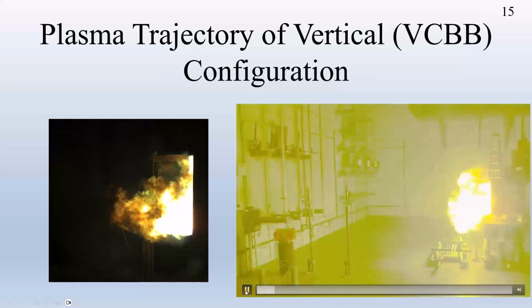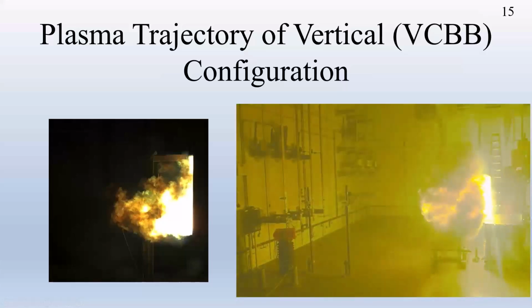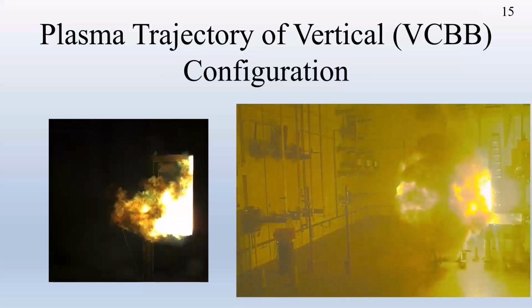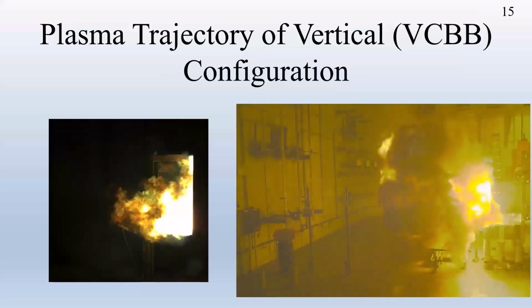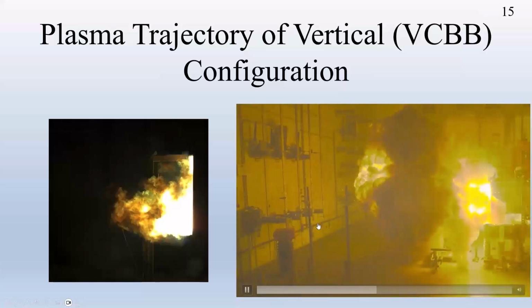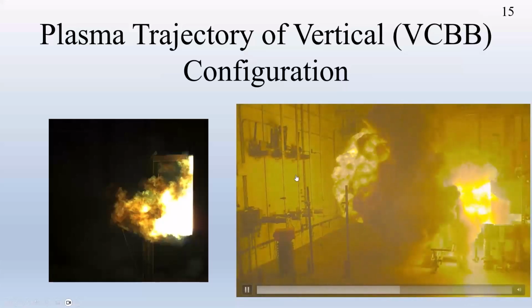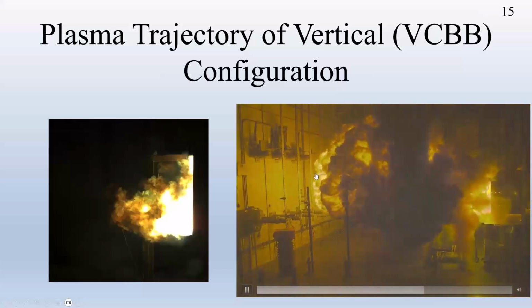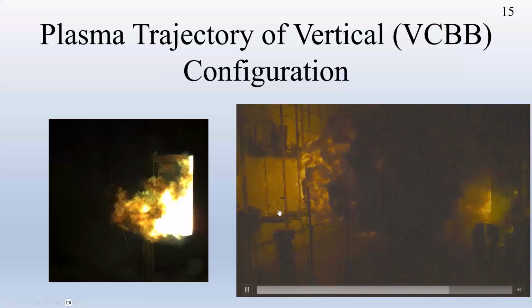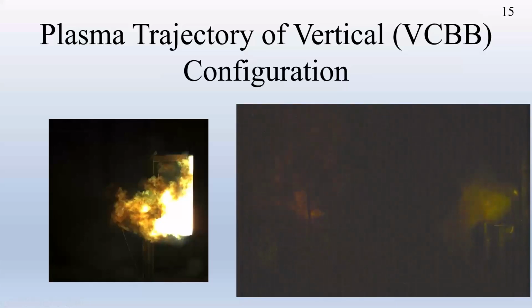And this is the VCBB configuration over there, and you can see this is 4.16 kV with 63 kA. One thing I have to mention is that you are going to see a metal droplet here, and from the measurement point of view, we won't be able to measure the metal droplet. It's a hot spot. So this is another thing that you have to consider.